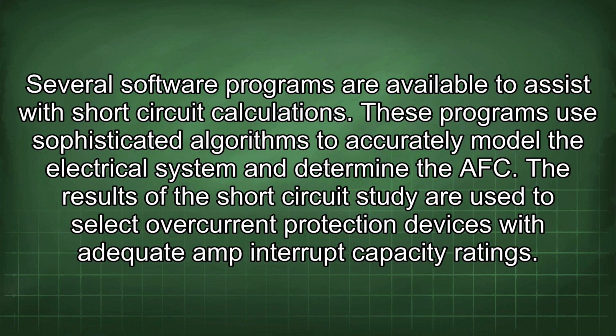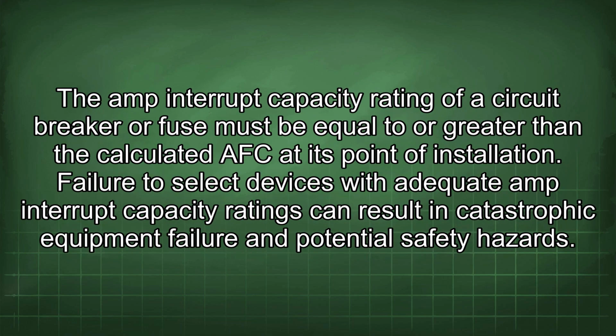The results of the short-circuit study are used to select overcurrent protection devices with adequate amp interrupt capacity ratings. The amp interrupt capacity rating of a circuit breaker or fuse must be equal to or greater than the calculated AFC at its point of installation. Failure to select devices with adequate amp interrupt capacity ratings can result in catastrophic equipment failure and potential safety hazards.